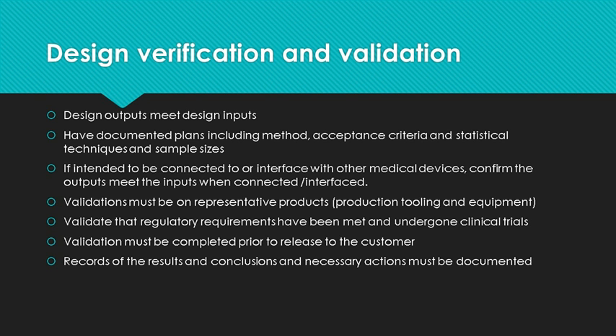Validations must be representative product. That must be off production tooling and equipment, not pre-production molds. Validation, you must validate that regulatory requirements have been met and undergone clinical trials. Validation must be completed prior to release to the customer. Records of the results and conclusions and necessary actions must be documented.